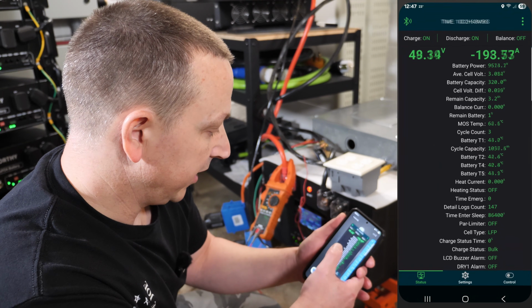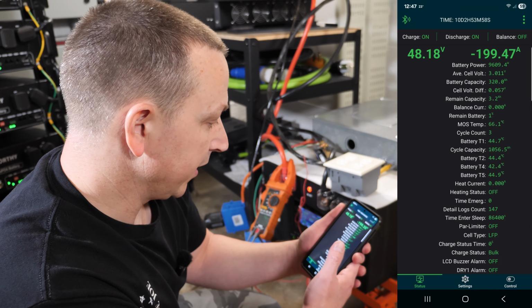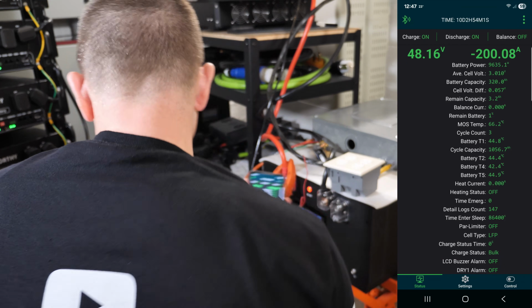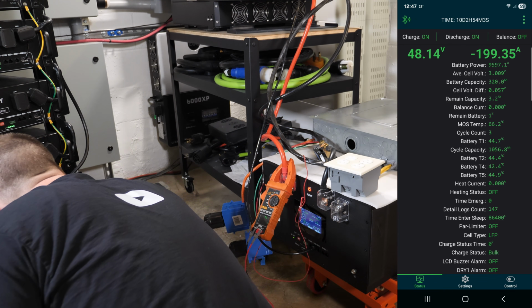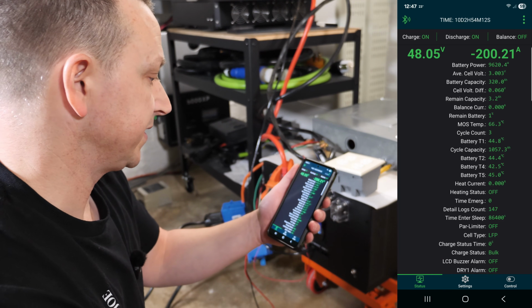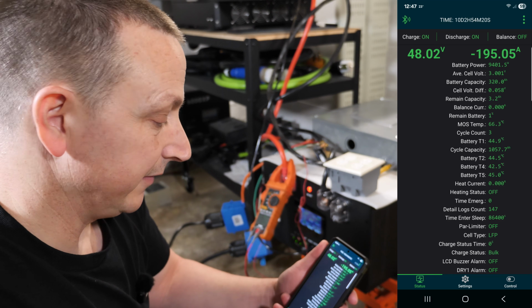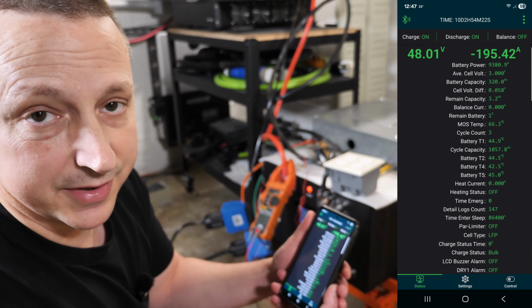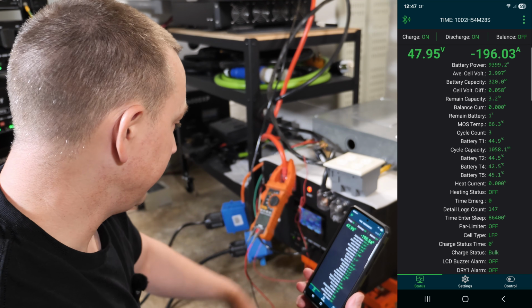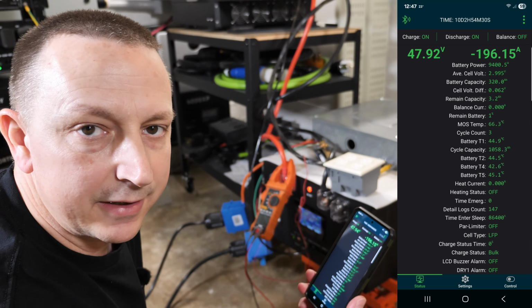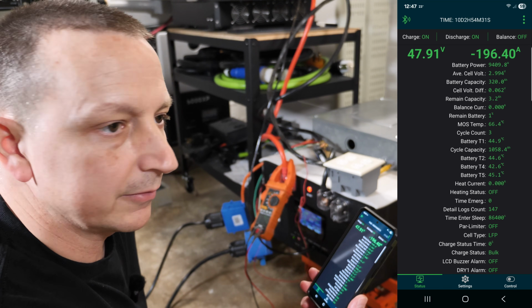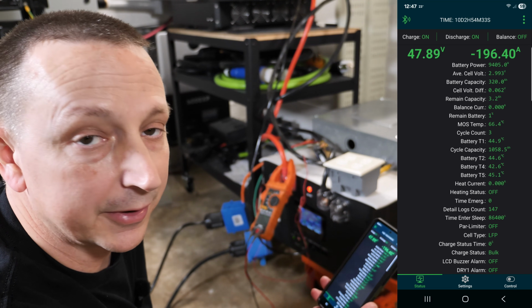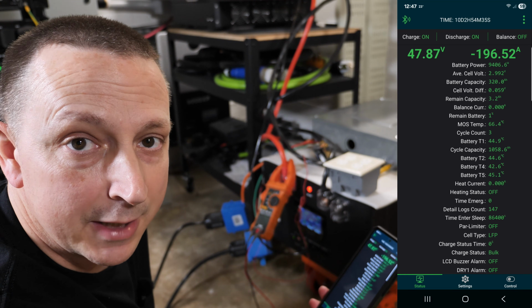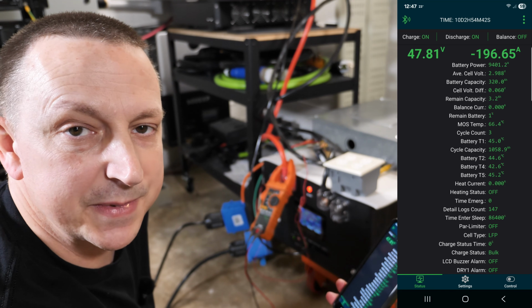But I do want to hop over here on the JK real quick. We're at 199 amps. I'm actually going to lower this down a little bit so we can stay under 200 amps, which I might have to lower even more when the voltage starts going down. I don't know if this capacity test is going to be accurate, because I don't know if the shunt remembered what it was before, and I wasn't here during that time because I didn't think it was going to shut down. I was actually upstairs eating.